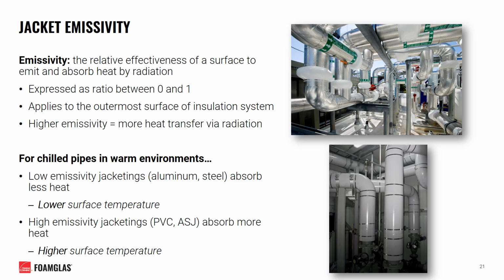Another design consideration of your insulation system that should not be ignored involves the emissivity of the outermost jacketing to be used. Emissivity is the relative effectiveness of a surface to emit and absorb heat by radiation. It is expressed as a ratio between 0 and 1 and is most relevant to the outermost jacketing to be used on an insulation system. The higher the emissivity, the more heat transfer will occur between the material and its environment via radiation.